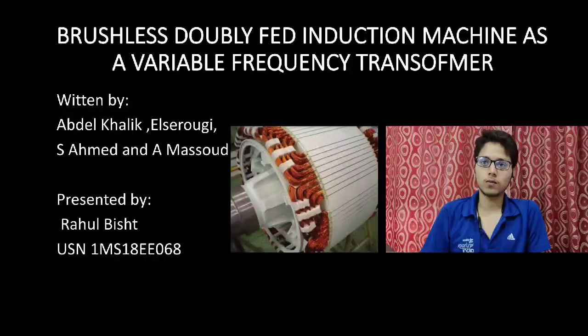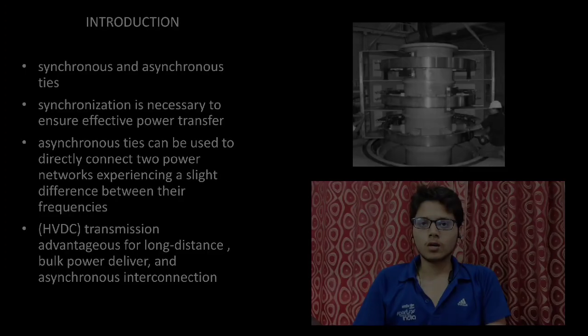the bulk power transmission. The brushless doubly-fed machine BDFM with the nested cage rotor machine is proved to be a comparable alternative to conventional DFIM in many applications, with the advantage that all the windings being in the stator frame with the fixed output terminals.